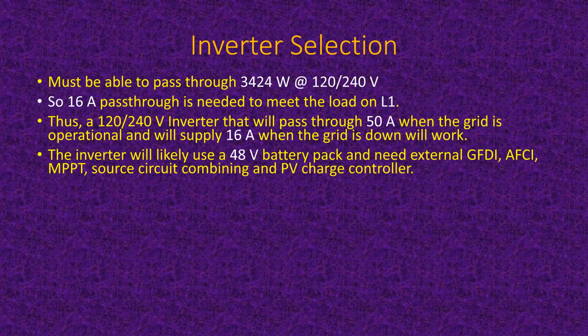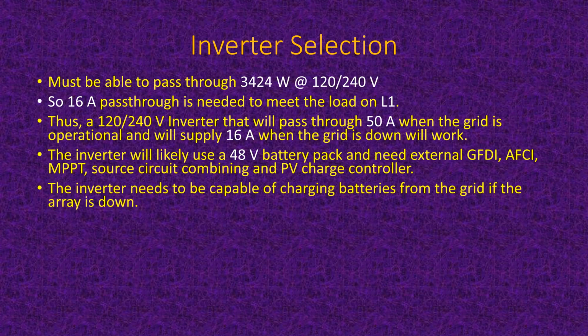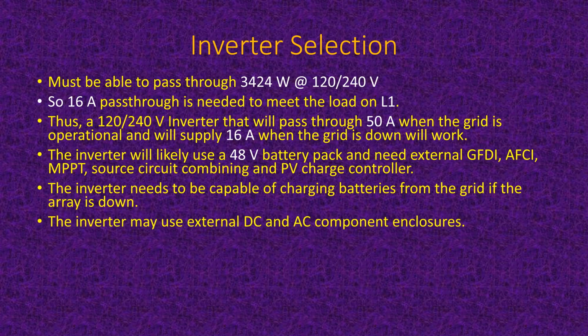More than likely, it'll use a 48 volt battery if it's a 10-year-old system and needs some external storage. If it's a battery pack that's currently being used in the integrated systems, it's going to be more like a 400 volt battery pack. But in any case, 48 is what it used to be. When you're paying attention to your design, you're going to look at the power rating, the voltage rating and the current ratings on your battery packs. And the inverter has to be capable of charging batteries from the grid if the array is down, like at night, and most do that.